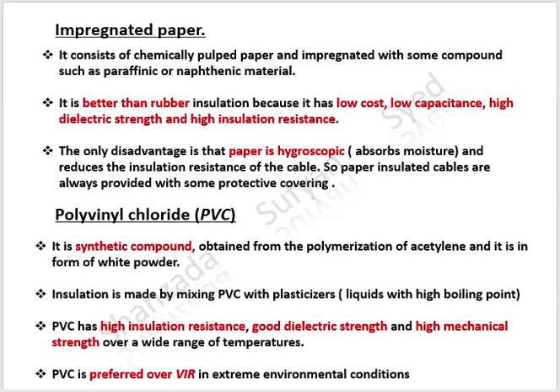Next is impregnated paper. It consists of chemically pulped paper impregnated with compounds such as paraffinic or naphthenic materials. Impregnated paper is better than rubber insulation because it has low cost, low capacitance, high dielectric strength, and high insulation resistance. The only disadvantage is that paper is hygroscopic — it absorbs moisture and reduces the insulation resistance of the cable. So paper insulation is always provided with some protective covering.